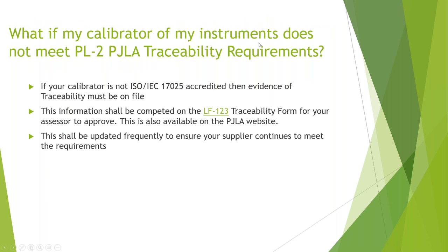What if your calibrator of instruments does not meet PL2, which is our traceability policy requirement? Our policy requires you to use accredited sources, but in some cases the person doing the calibration — perhaps the manufacturer — is the most competent and doesn't want to become accredited. There is an exception for not using a 17025 accredited lab for calibration, where you'd have to ask them to fill out our traceability form, which will be reviewed during your assessment. If we see the calibration lab isn't accredited, we'll ask why — and if you explain it's the manufacturer, we still want some type of traceability form to demonstrate traceability.